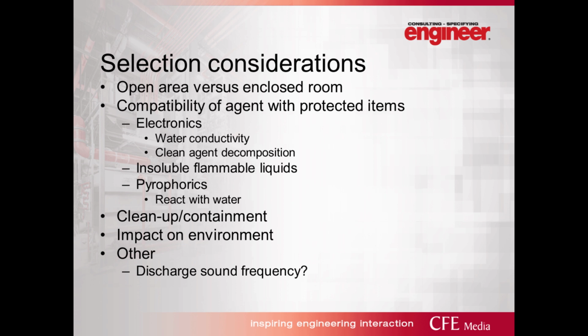Open versus enclosed room, I talked about this a little bit as well. Certain suppression agents are good for one versus the other. Compatibility of the agent with protected items is very, very important. Electronics don't play well with water. That doesn't mean that you can't protect electronics with water, but you'll want to try to protect them with something else better, especially if they are very important for data or things like that. Pyrophorics react with water and therefore don't deal very well with water-based suppression agents.